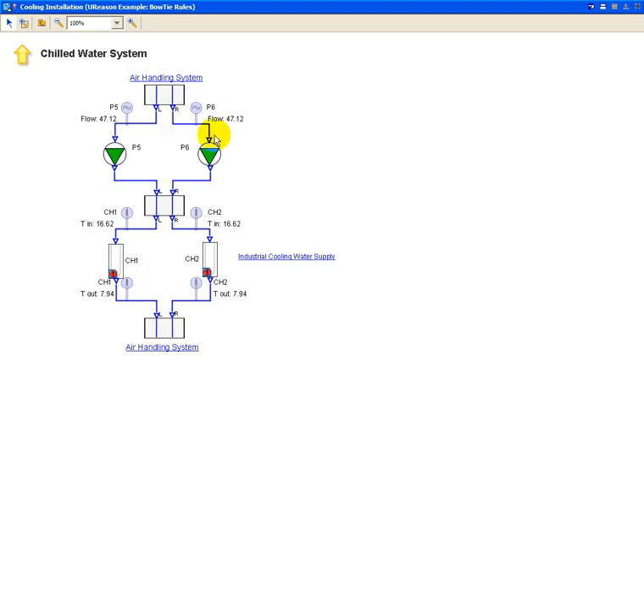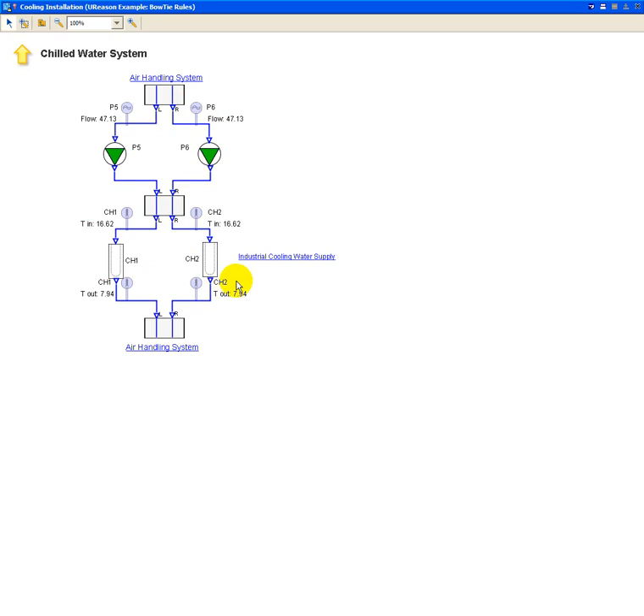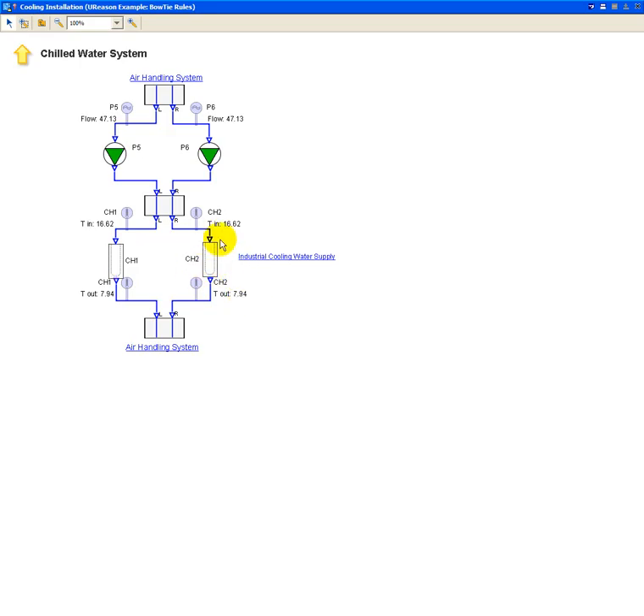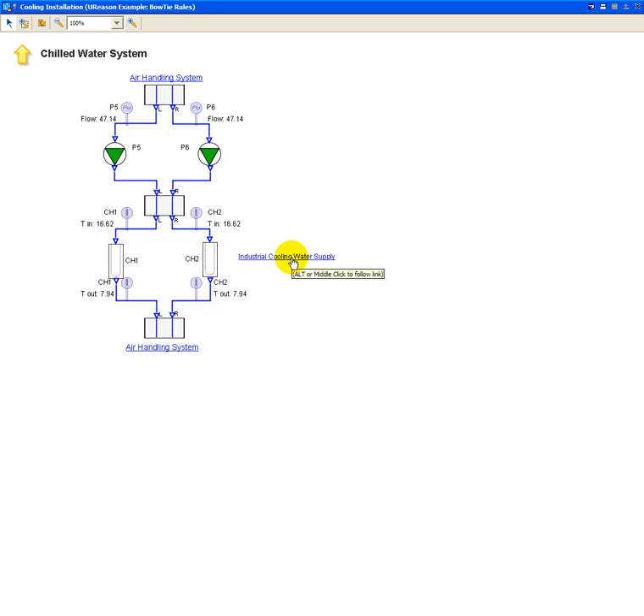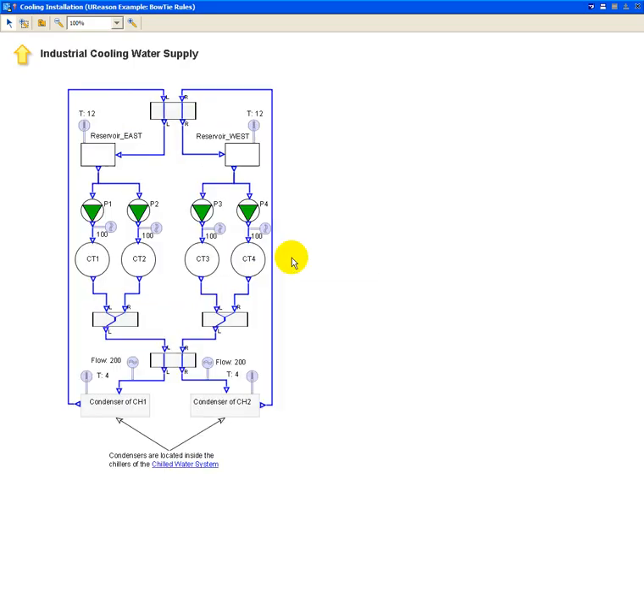And there we can see we have two twin lines here, each consisting basically of a pump pushing the flow, the water flow inside a chiller here. That will reduce the temperature of that water from 16.62 to almost 8 degrees. And these chillers have, inside of them, condensers, and these condensers are part of the industrial cooling water supply unit, so I can navigate to that unit also by clicking on this link.